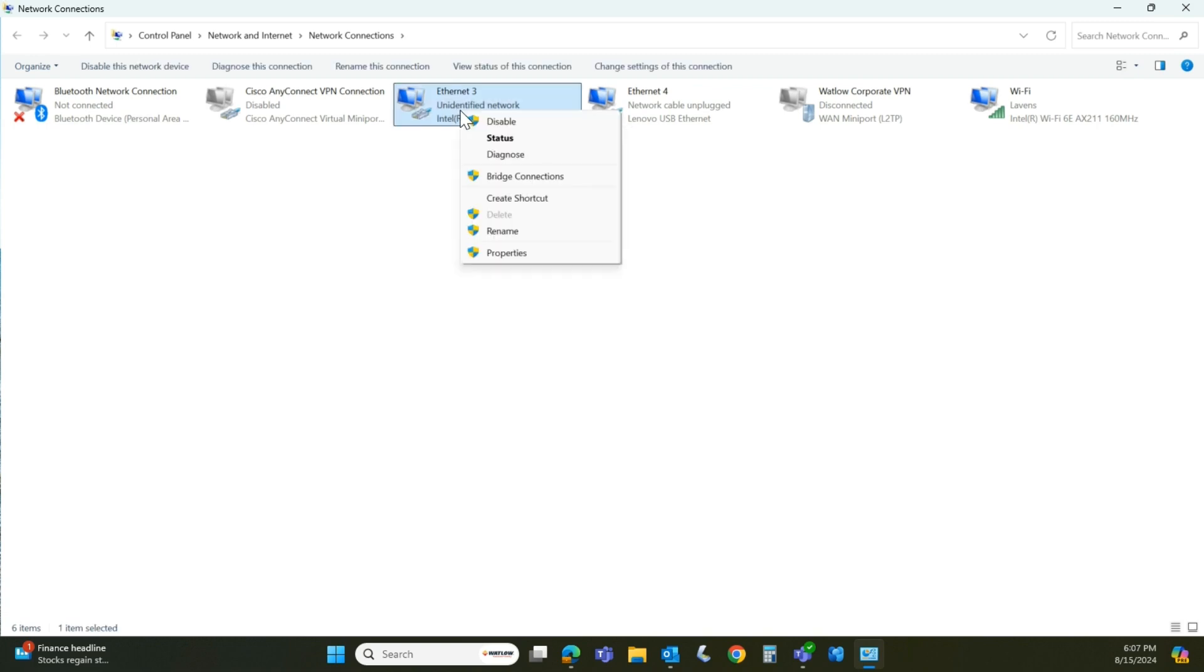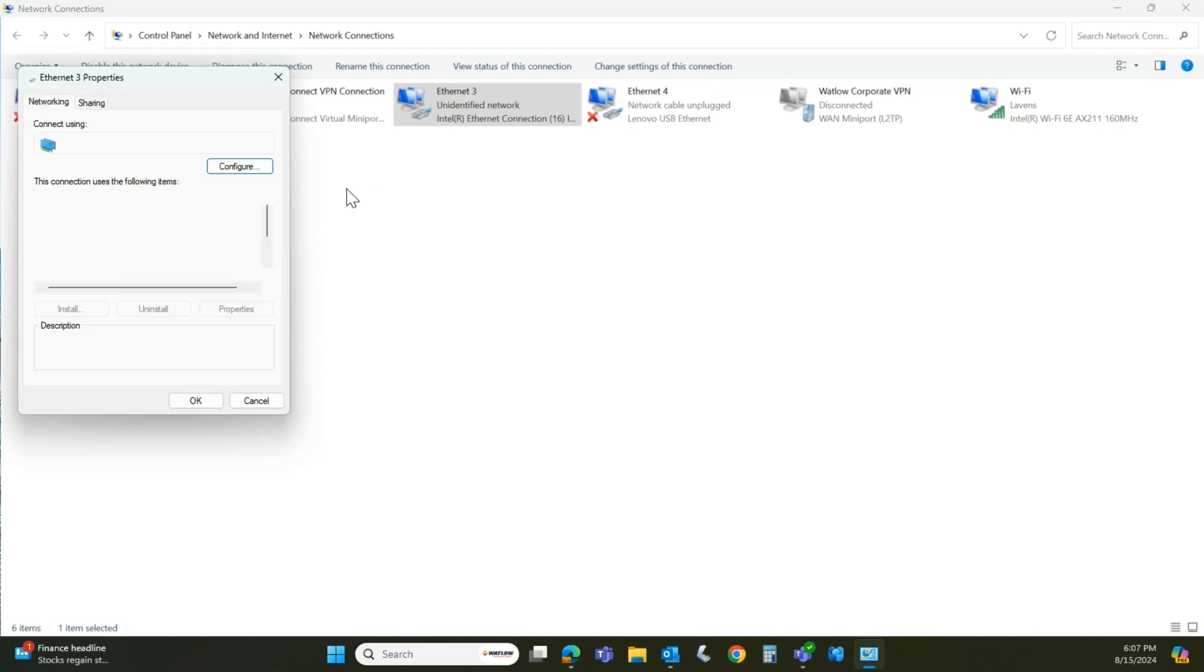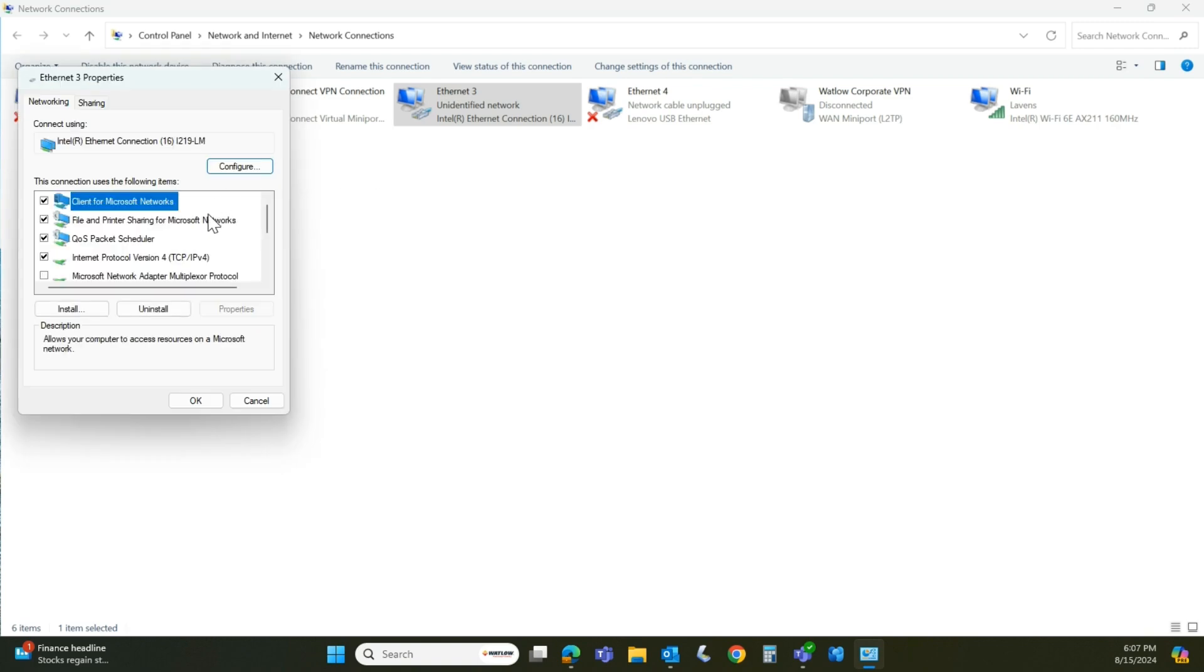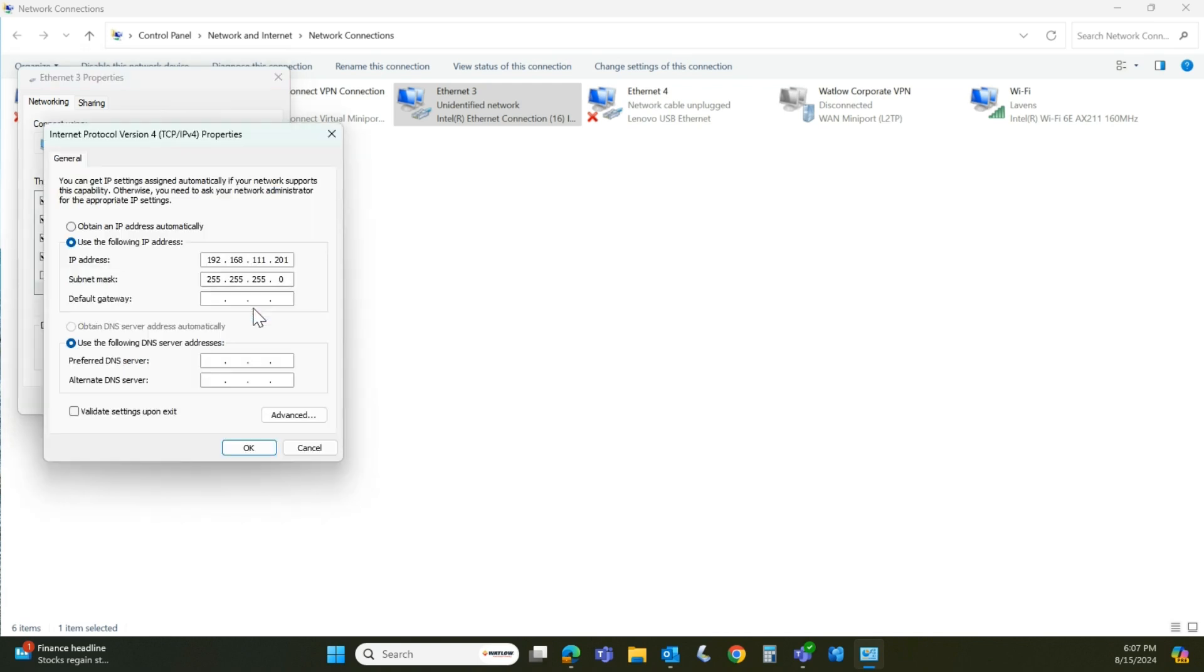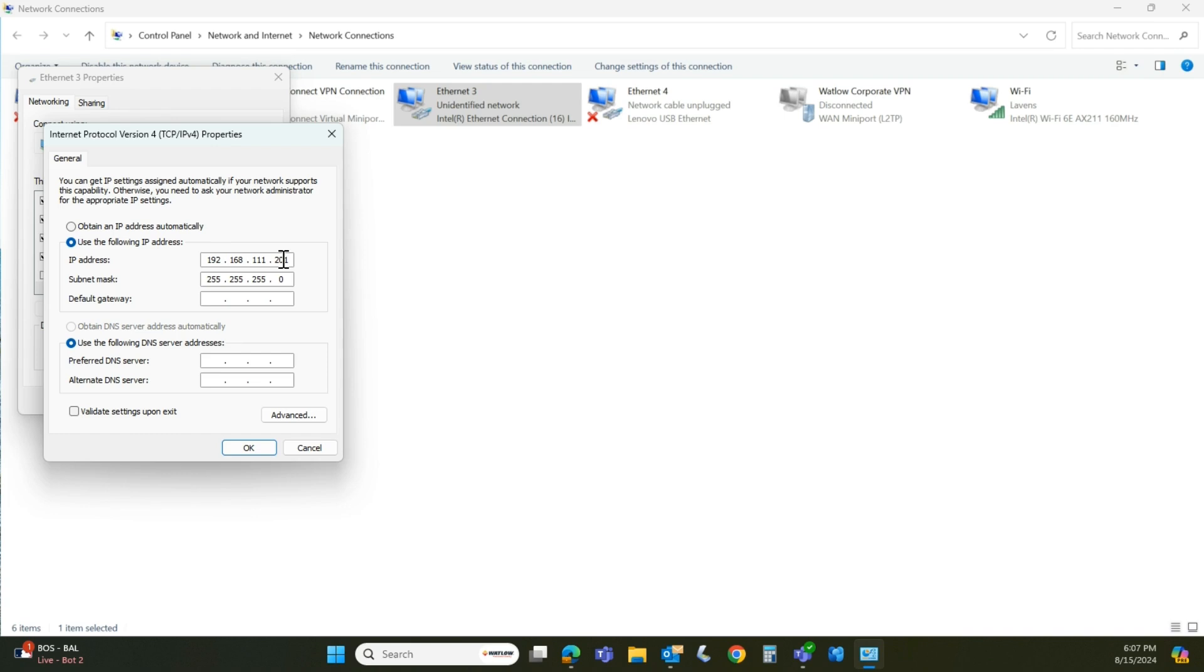If I left click on this and go to properties. There's Ethernet three properties. I want to look for this internet protocol version 4 and hit properties again. This is the IP address of my PC. So same sequence 192, 168, 111. But the last field cannot be the same as the instrument.